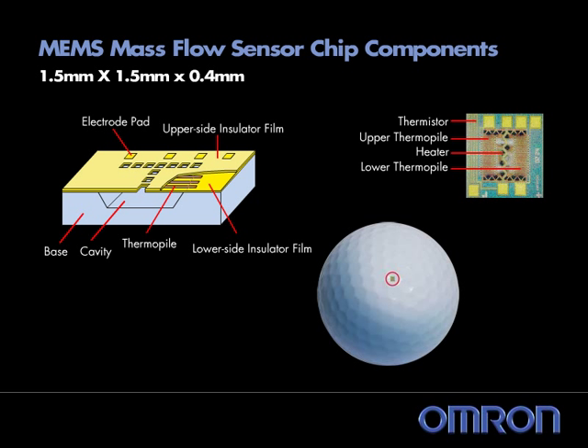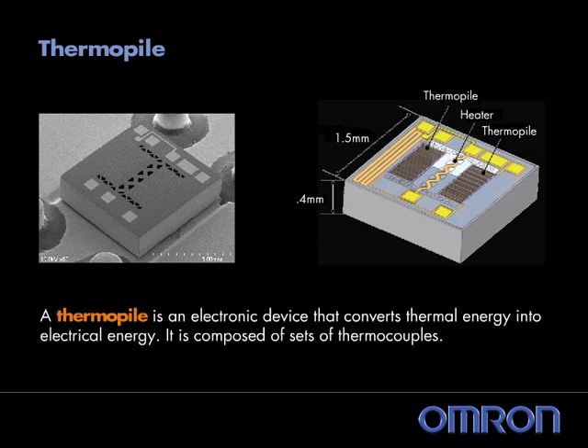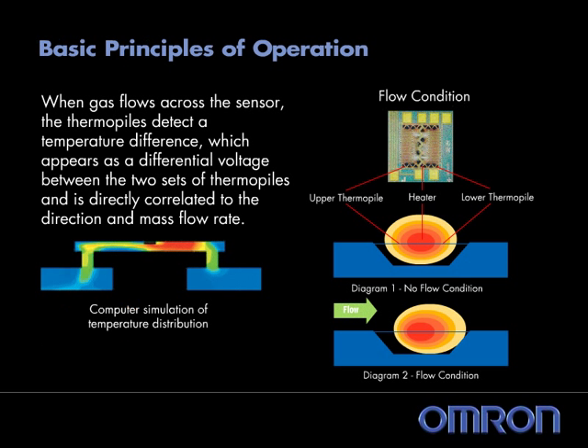The chip components include a thermistor to regulate the heater temperature and two sets of thermopiles located below an insulating film and the electrode pads. The thermopiles are devices made up of several miniature sets of thermocouples used to convert thermal energy or temperature differences into electrical signals.